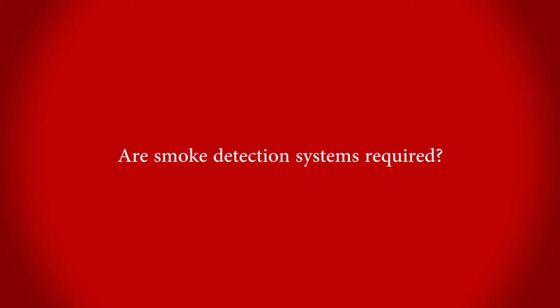Smoke detection is not always required in business occupancies. If that lever is not working and you don't have smoke detection, then there's a problem and we need to get the fire alarm checked out by a licensed fire alarm company. Now, regardless of the occupancy, a fire alarm panel, the main brain for the system, is required to have a smoke detector located in proximity to it. Thereby, if there is a fire in that room, the smoke detector will go off, alert the system, and put the system into alarm before it burns up. So that's the idea of that. If you pull that station and it doesn't work, you're going to have a problem with your fire alarm system, and it needs to be examined.